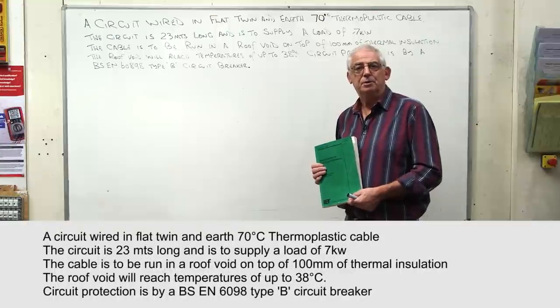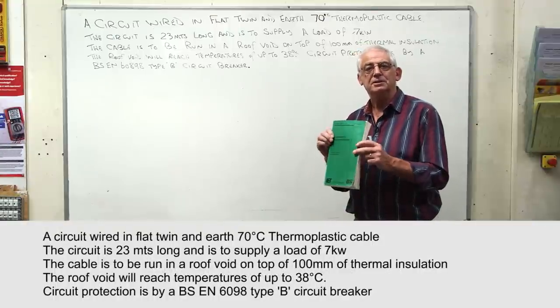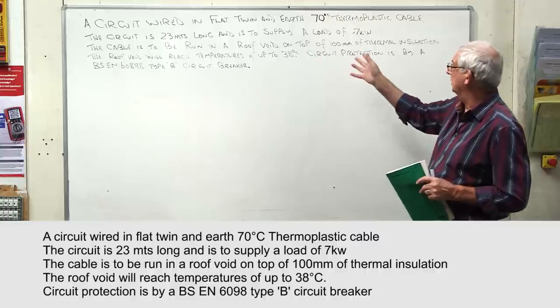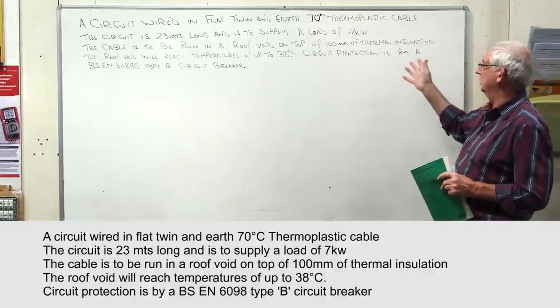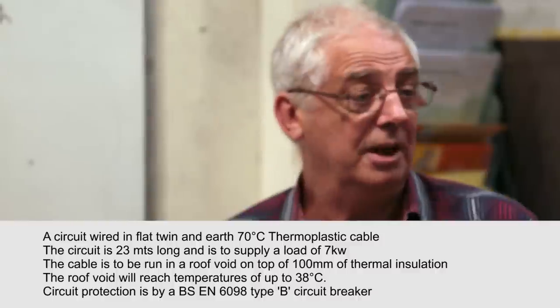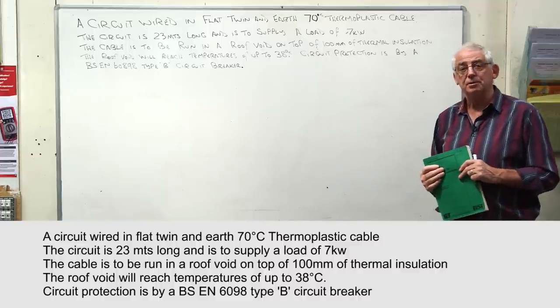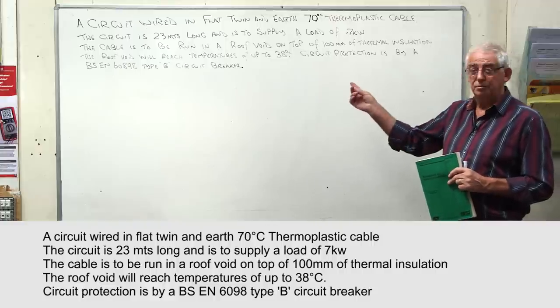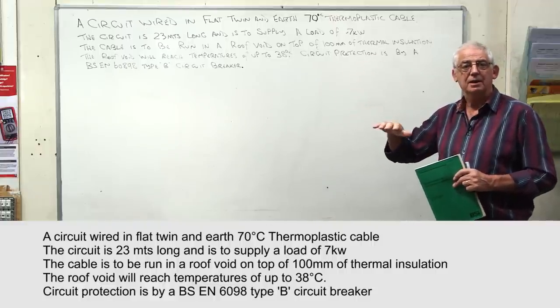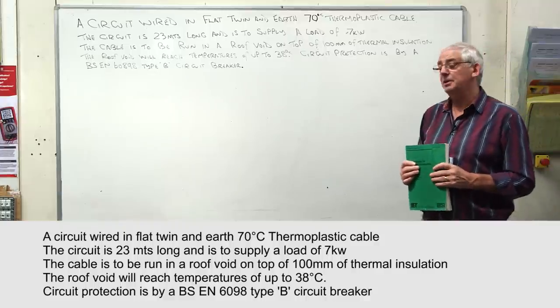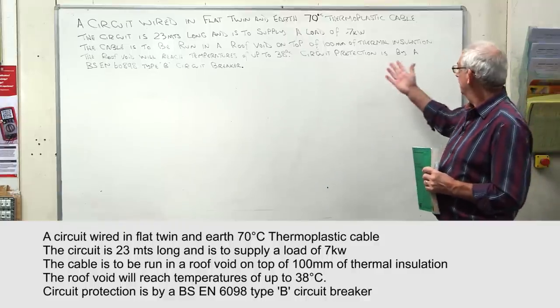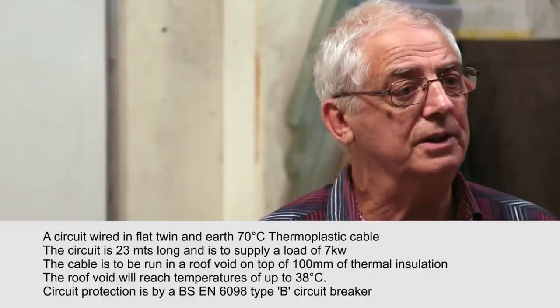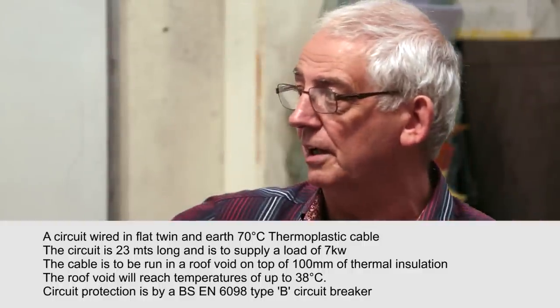I'm going to demonstrate how to carry out a simple cable calculation using the tables from BS 7671. The question on the board says: a circuit is wired in flat twin and earth 70 degree thermoplastic cable, 23 meters long, to supply a load of seven kilowatts. The cable is to be run in a roof void laid on top of 100 millimeters of thermal insulation, and the circuit protection is a BS EN 60898 Type B protective device.